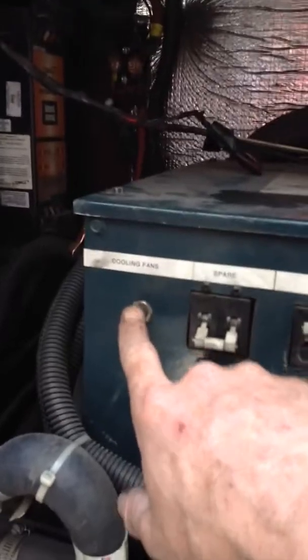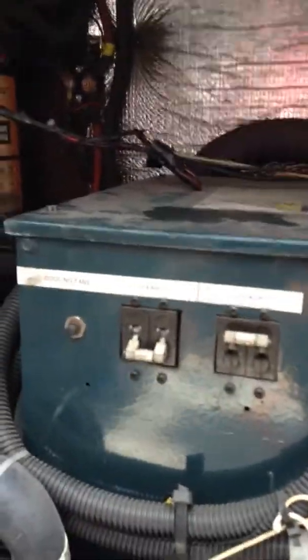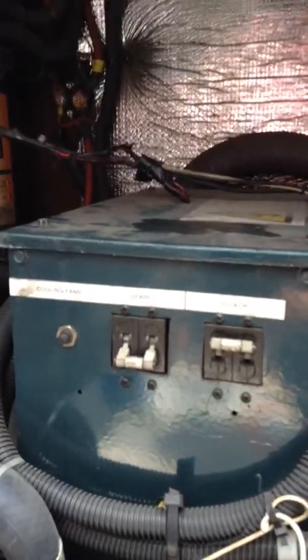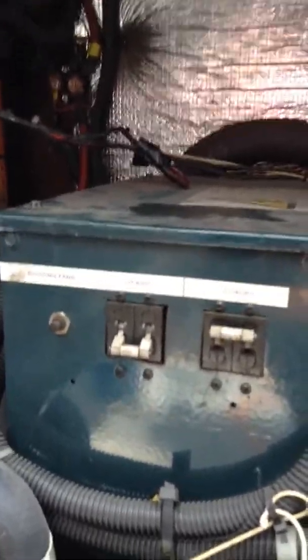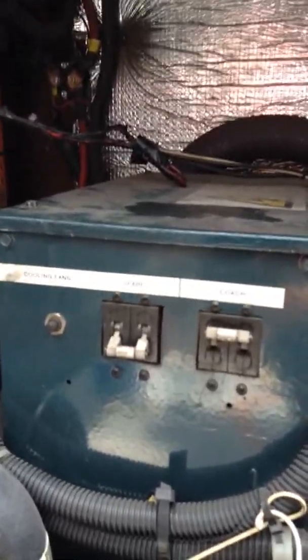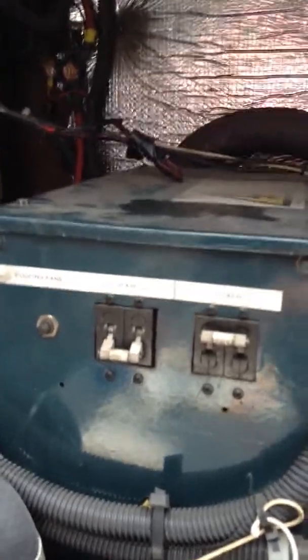You have circuit breakers, they're marked. One for the coach, this is a spare. This one is marked cooling fans. There are 2 cooling fans on this generator. If either one of those fans are not in operation, the generator will overheat and shut itself off.